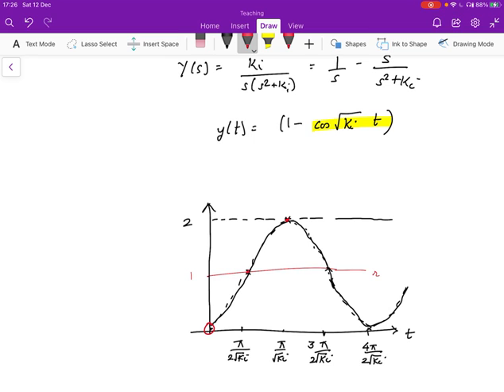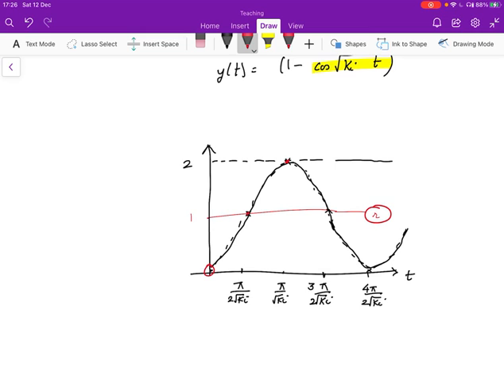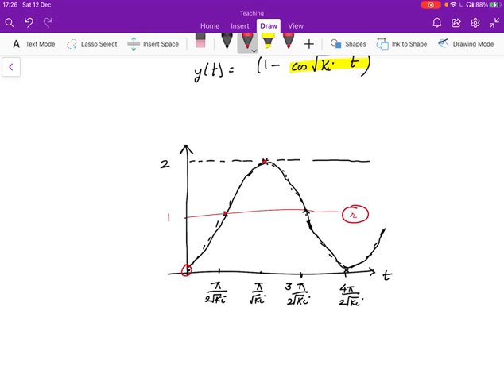And this means that though we want to be at this value over here, what you're actually going to get is an oscillating sinusoidal signal, which is why we say that with integral mode control, we are going to have the ability to look at the accumulated error, but we in fact end up with oscillatory control. So we never use integral mode control on its own. It always needs to be combined with proportional and derivative control.